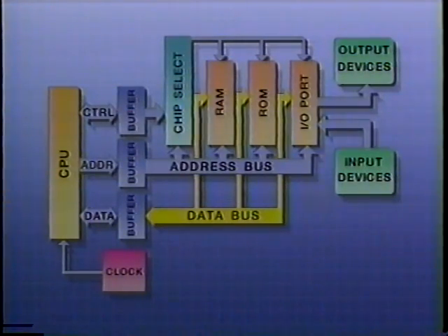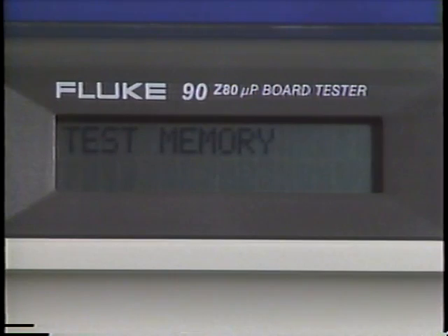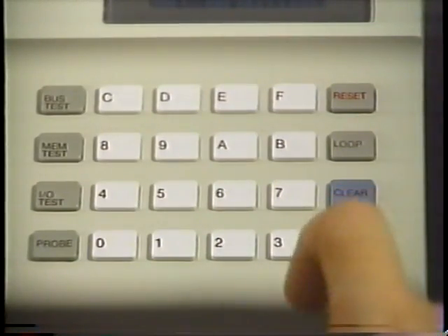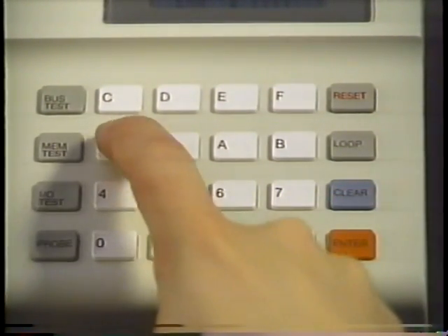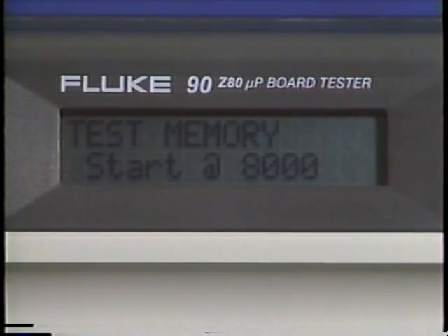The Fluke 90 offers 6 memory tests. 2 of these tests, test memory and memory checksum, are best used to confirm that your UUT's RAM and ROM are functioning properly. Let's use test memory as an example. Test memory should be used to check the UUT's RAM. To run the test, select Test Memory and press Enter. Select a start address. Then press Enter. Select the end address and press Enter once more.